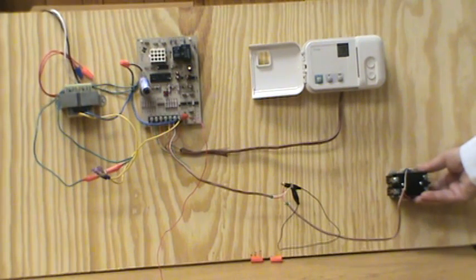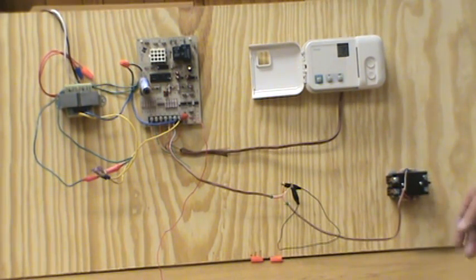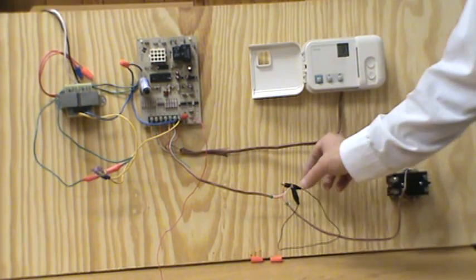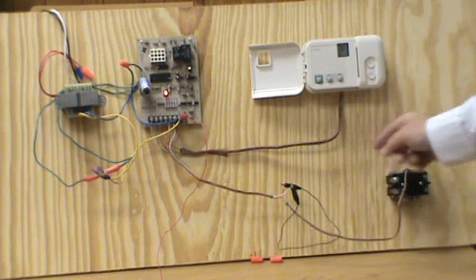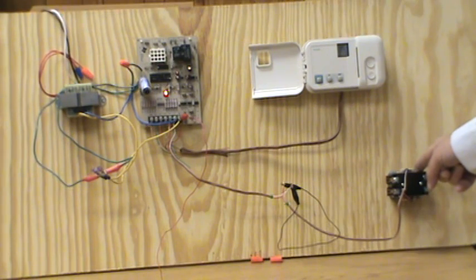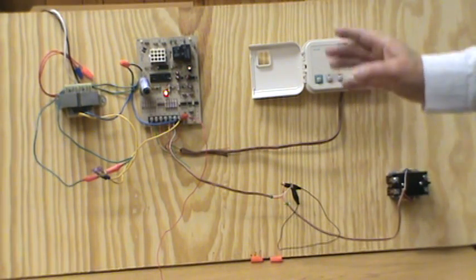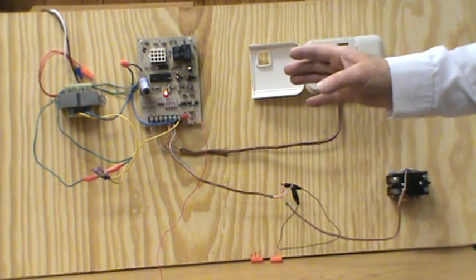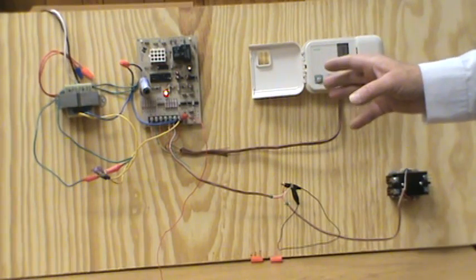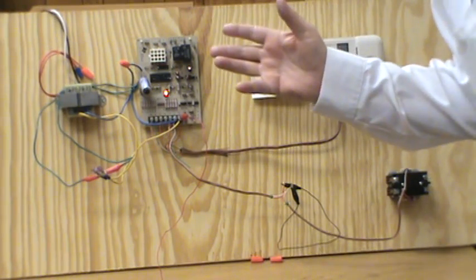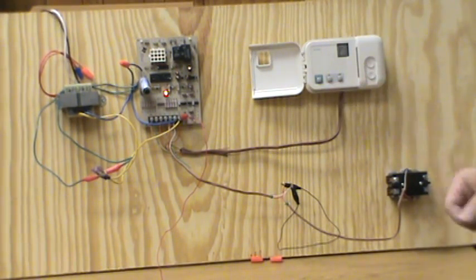And what I've done, we're going to go ahead and demonstrate a direct short on the wiring going out to the condenser on the cooling circuit. And we can show you how easy it is to use the Short Pro to isolate that circuit that's got the short and find out exactly where it is. Is it the wiring in the attic or is it at the condenser?